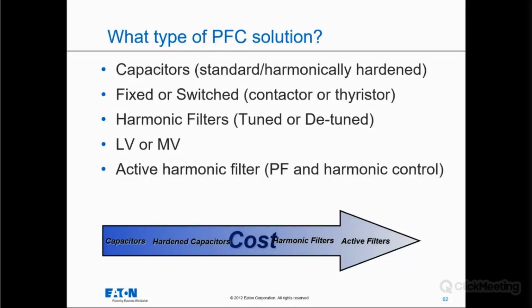If you have a harmonic environment, you may need a tuned or detuned or filtered bank. There's a lot of words for that. And manufacturers also make low voltage and medium voltage. So again, it really determines the type of loads in your facility, whether low voltage or medium voltage would be right for you, and what voltage you take delivery from your utility at. And then finally, if you have a really bad and nasty harmonic environment, you may want an active harmonic filter to filter out the harmonics in your facility to give you a clean sinusoid.